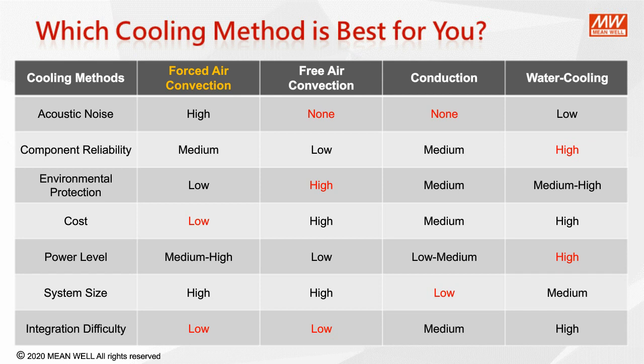For power supply unit cost, forced air convection, also known as fan cooled, is generally the lowest. For the next 2 categories, water cooling has the highest potential power level potential, and conduction cooling type has the best potential for keeping system size small. And lastly, forced air convection and free air convection types are easiest to design with, so they're the most common types as well.